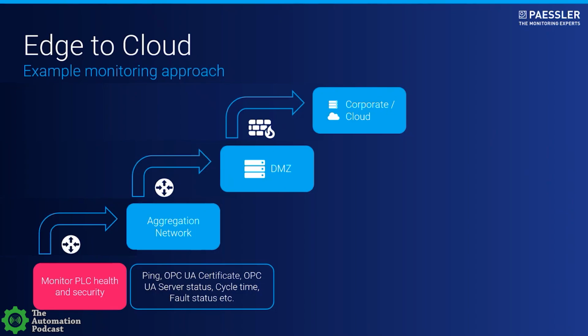If you dig deeper into the PLC, like checking a certificate via OPCUA, or checking the OPCUA server status to know if it's really up and running, if you can actually collect data from the system, you might check the cycle time tags, or if there are any fault status tags on the PLC, so you can pull them into our system to ensure the field level, the PLC control level, is up and running.